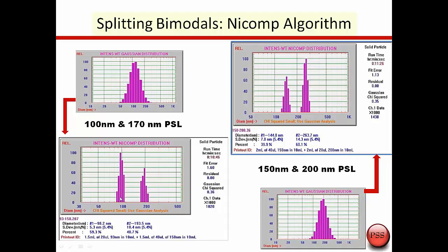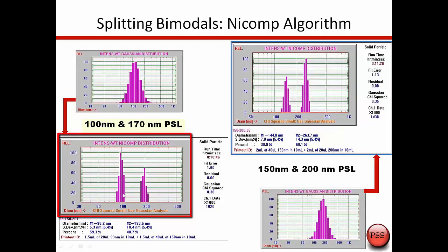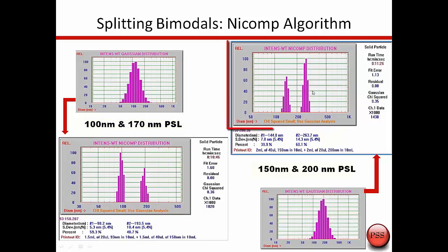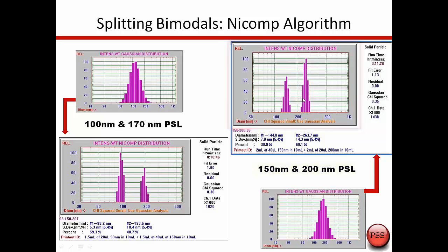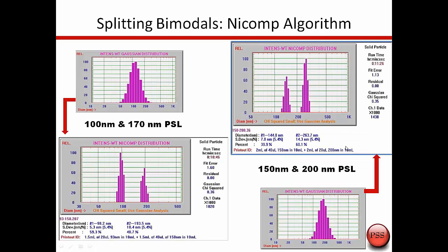If you look at taking two polystyrene latex standards that are 100 and 170 nanometers, using a Gaussian distribution you'd just create a smooth curve between the two. But using the NICOMP distribution, we can actually split these two peaks. We believe we have the most sensitive algorithm for splitting peaks that are fairly close to each other — here splitting PSLs at 100 and 170nm, and here 150 and 200 nanometers into their individual peaks.